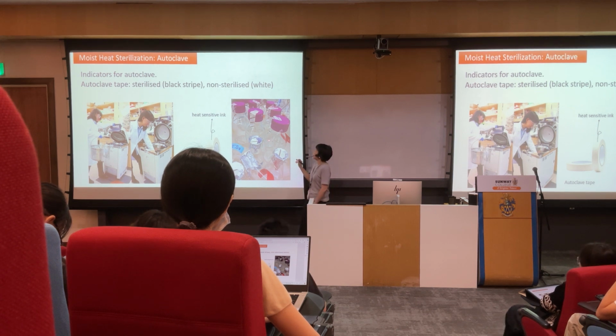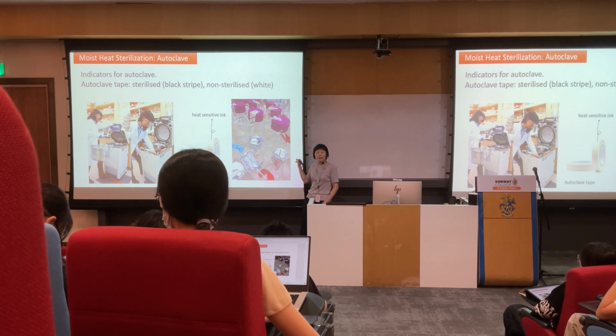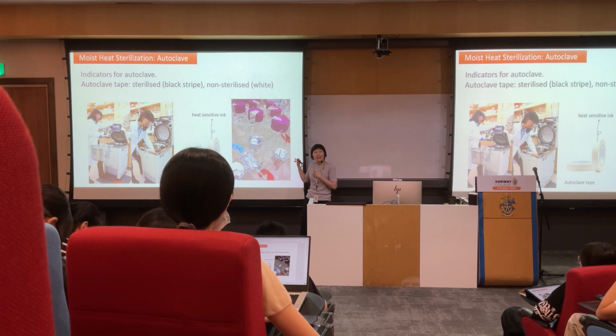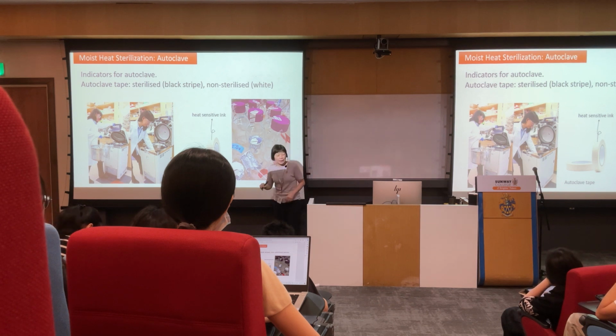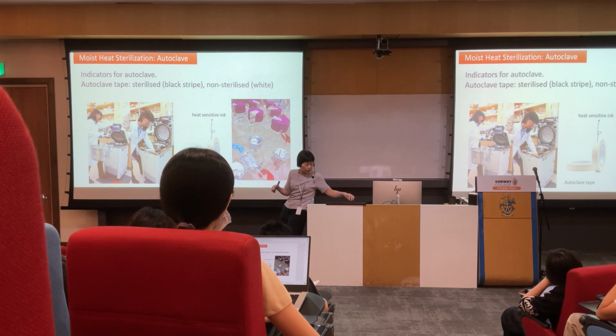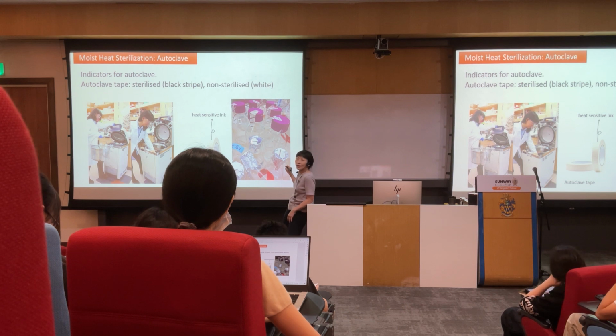However, this tape is actually outside the bottle. How are we sure that inside the bottle is also effectively reaching the temperature and killing the bacteria inside the bottle? But normally we believe that whenever we tape it, it works. In the chamber, it should be able to remove everything from the bottle, unless you screw it very tightly. The steam cannot go in, therefore you cannot sterilize whatever is inside. So make sure that in future, whenever you sterilize your bottle, you release the cap slightly.